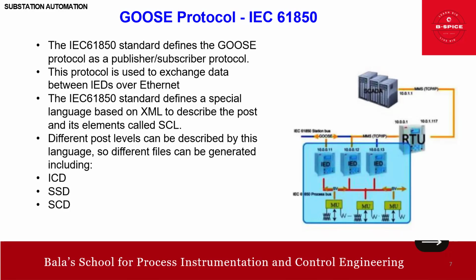It includes information about device function, data attributes, and communication capabilities. You would have seen a DD file, device description, in field instruments, right? Similarly, this ICD describes the capability and configuration of an IED. Then the ICD file is used to define the data sets and GOOSE control blocks that the IED can publish or subscribe to. This ensures that GOOSE messages are correctly configured and interpreted by all devices.